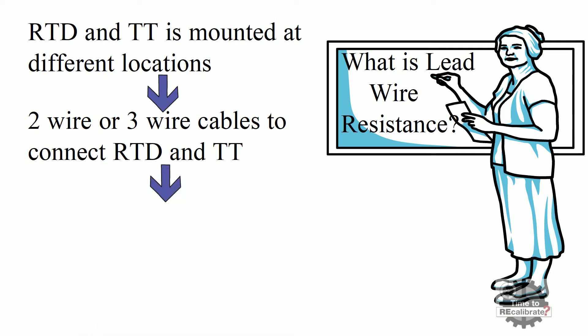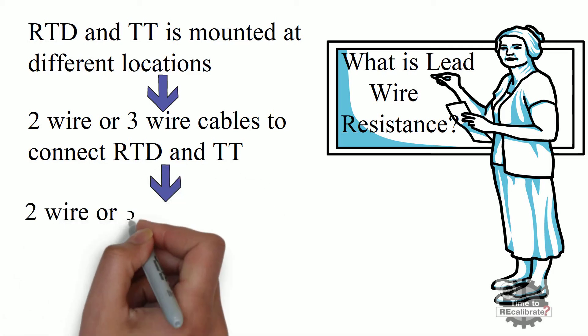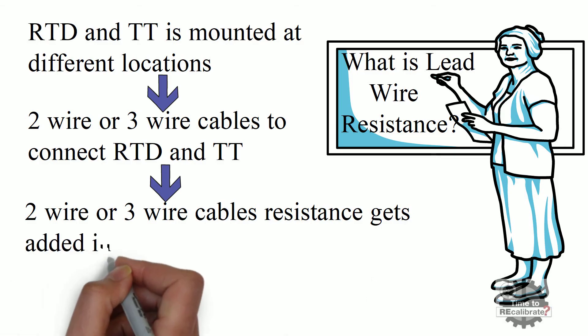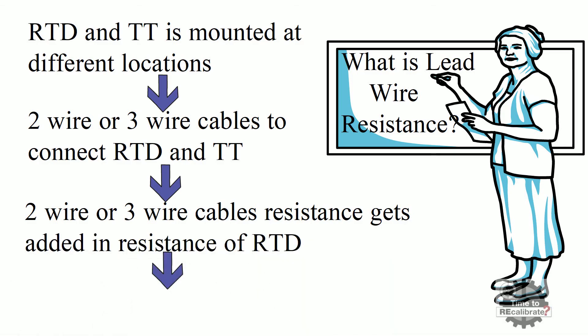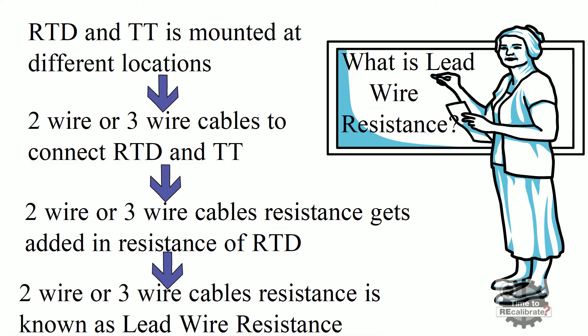These 2-wire or 3-wire cables have their own resistance, which gets added to the resistance of the RTD. These cables' resistance is known as lead wire resistance. These lead wires produce measurement error in temperature reading, which I am going to explain in the next slide.